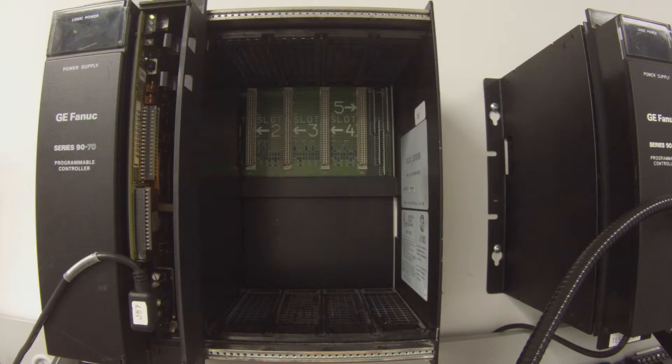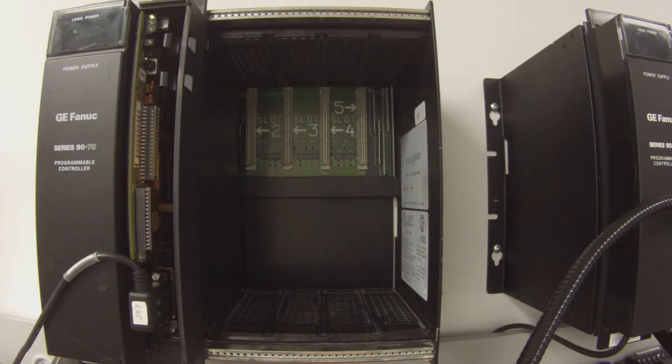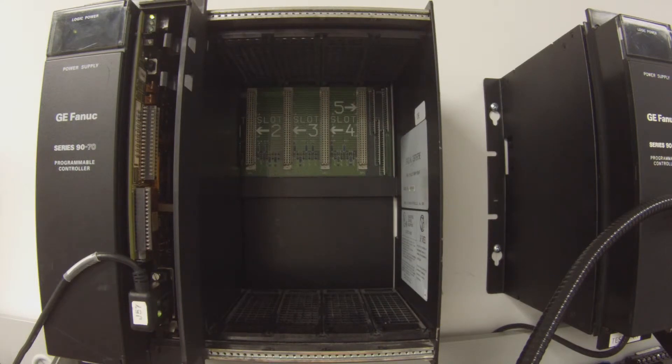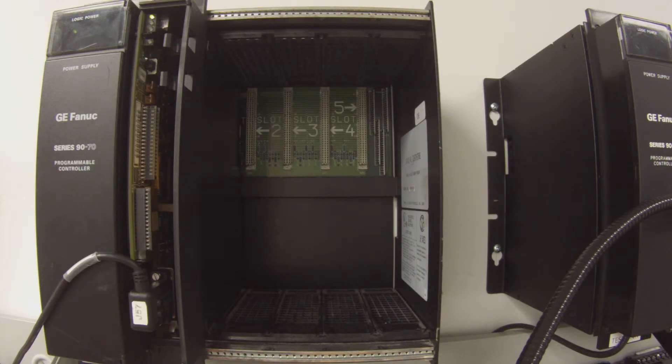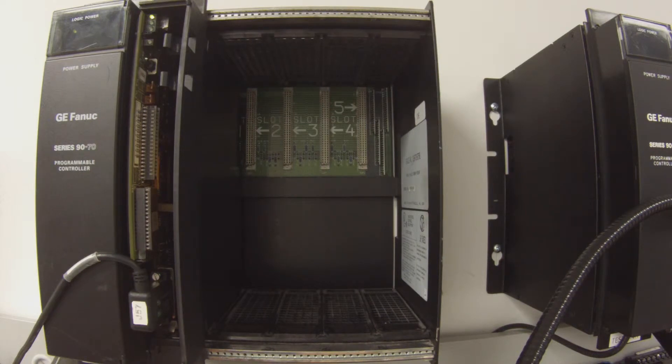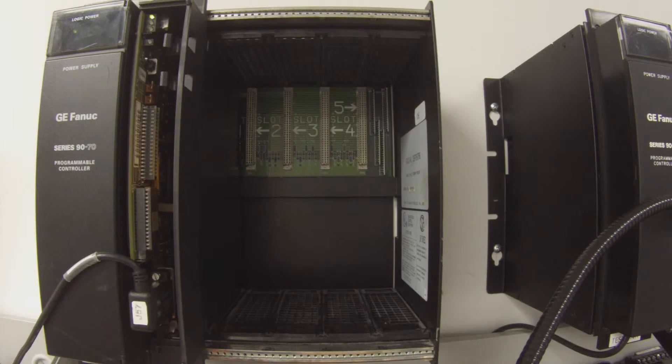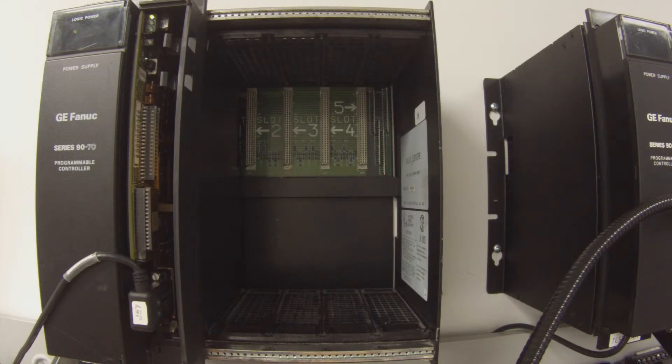Next thing I am going to do is on the top menu bar go to target, go to online commands in the middle, and when that pops open you want to go to clear. Now what you want to clear in this, you will need to do this to go any further. You want to clear controller fault table and IO fault table because your configuration being empty is going to be different than what it was before. You need to clear those before you can go any further. Make sure that you do not clear any memory related items because you may lose something that you need. Just stick to the bottom two selections, controller and IO fault tables. Clear those, OK.